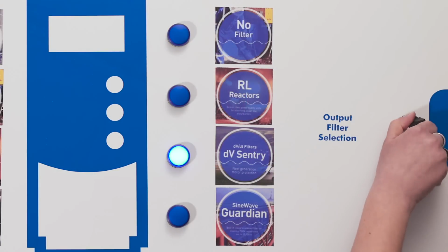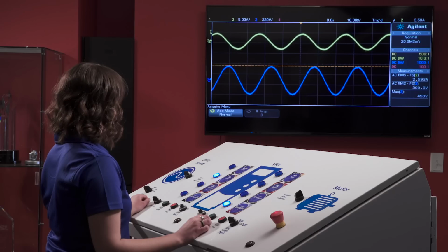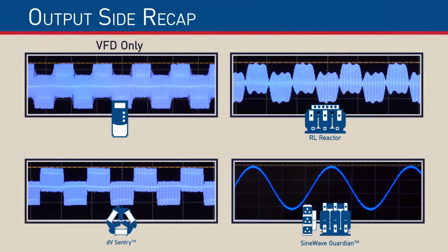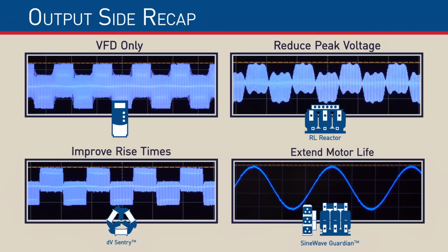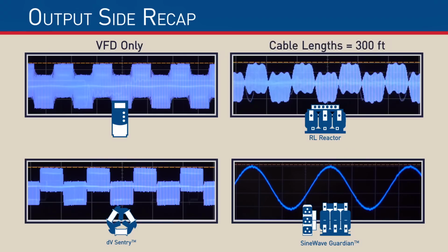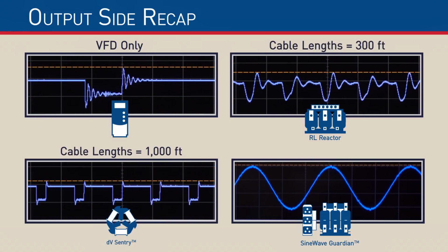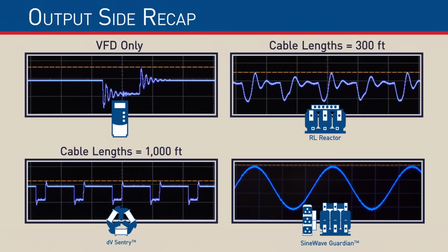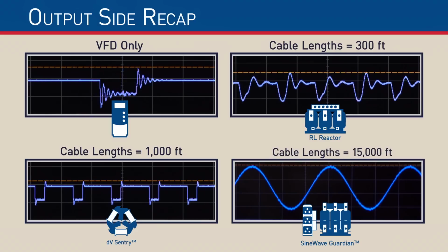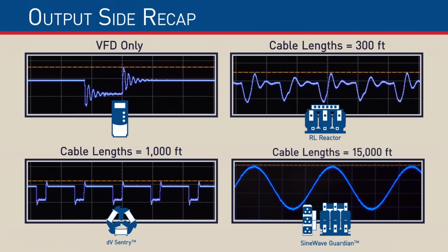When we add the Sine Wave Guardian back into the system with the same set of parameters, both the pulse width modulation and screeching noise virtually disappear. As we have just seen, MTE offers a variety of motor protection solutions to reduce peak voltage, improve rise times, or simply extend the life of your motor. The RL Reactor is your choice for cable lengths up to 300 feet. For cable lengths out to 1,000 feet, the DV Sentry is the perfect solution. The best-in-class Sine Wave Guardian has you covered out to 15,000 feet.